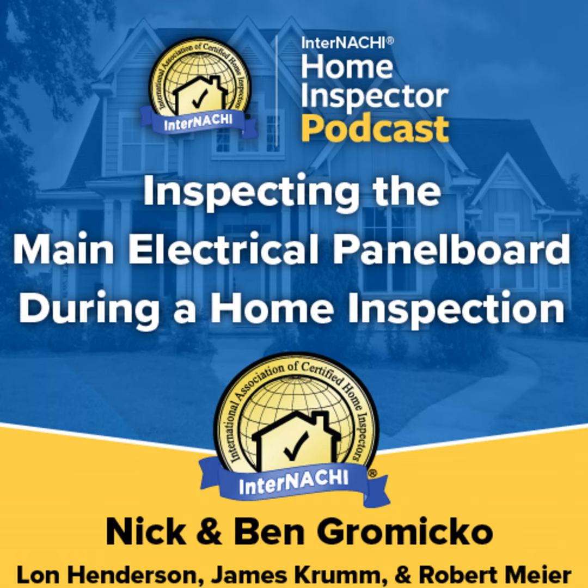The neutrals should not touch the grounds anywhere in the house except here at the main disconnect panel board. This is a safety feature that provides a separate path to the ground from the neutral conductor. The ground wires of the individual branch circuits can all be connected to the same grounding bar in the main panel. The ground wires carry the ground to each and every device, fixture, and appliance in the house.